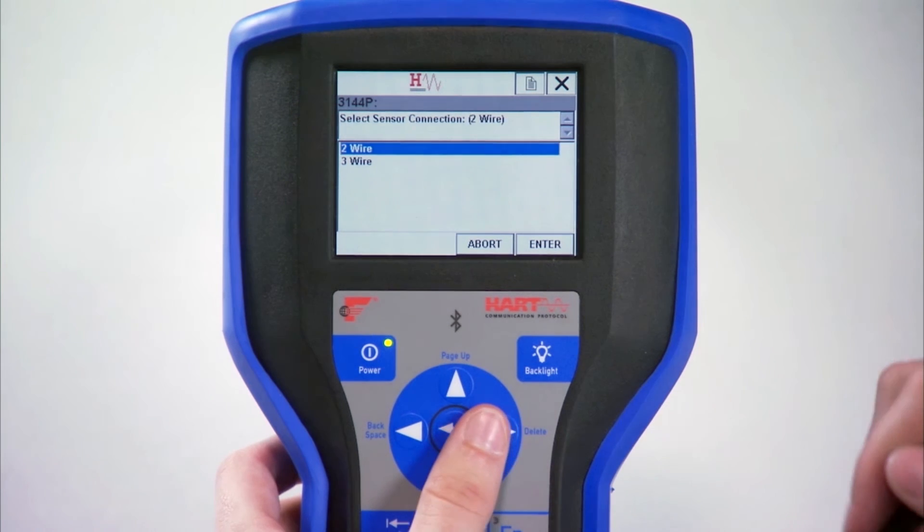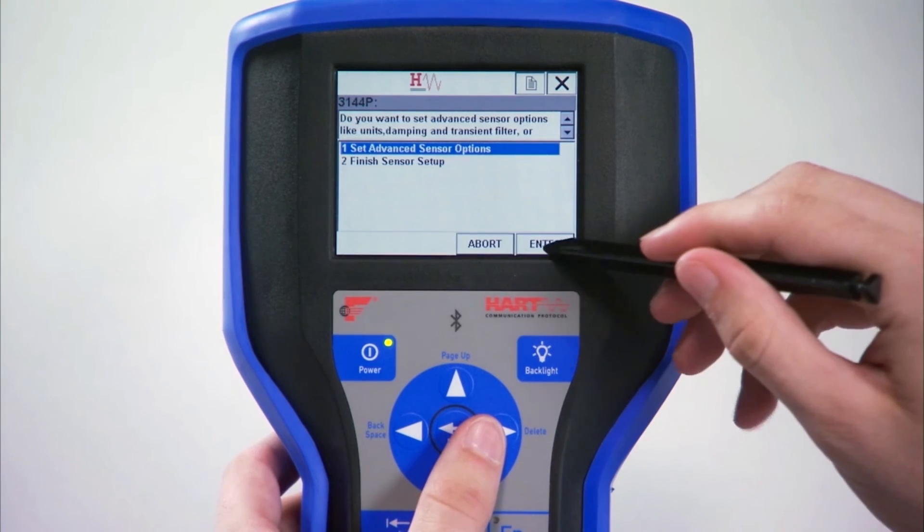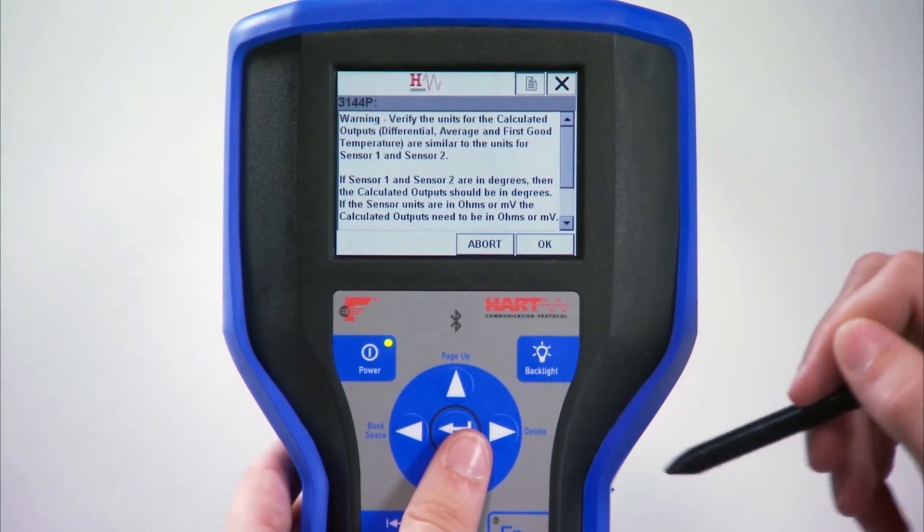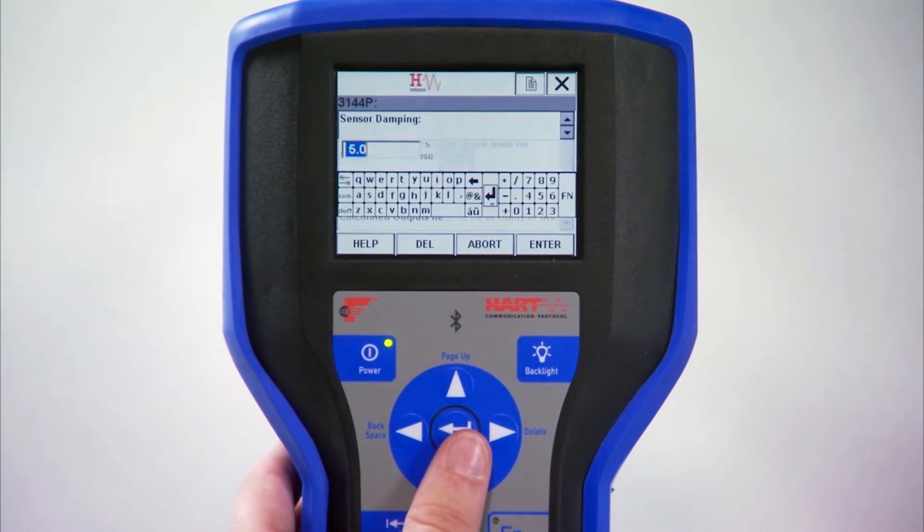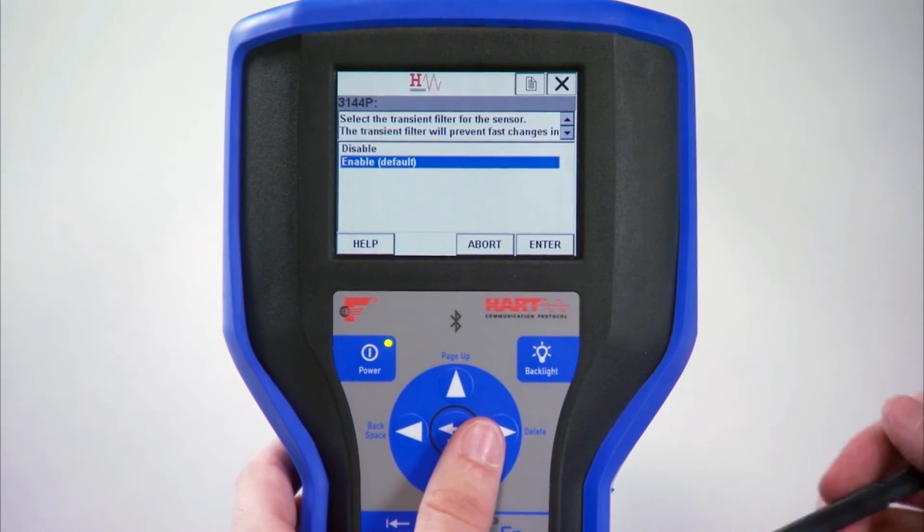Press Enter again to continue the configuration. Select your preferred engineering units and press OK on the following warning screen. Enter your preferred damping value and then select if you want the transient filter enabled.